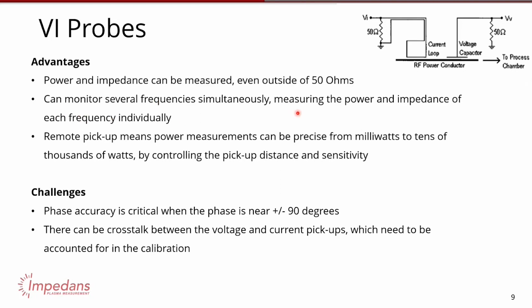And this is only possible, by the way, if you use the VI probe technology and you use Fourier transforms on the waveform. There's an alternative method called peak detection, but the peak detectors have the same issues as directional couplers. And the remote pickup means that power measurements can be precise from milliwatts to tens of thousands of watts by controlling the pickup distance and sensitivity. So being clever with the design means you actually get a much wider range of applications.